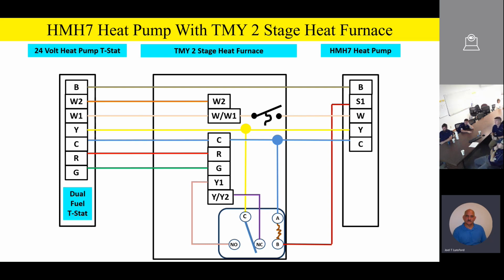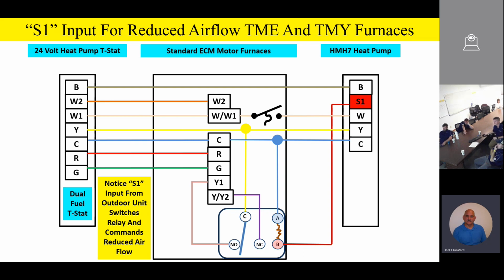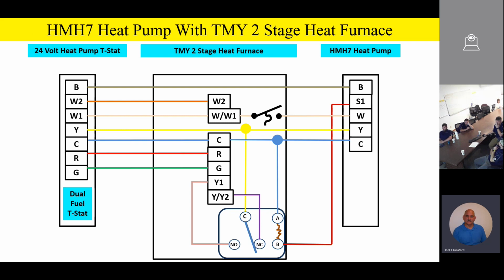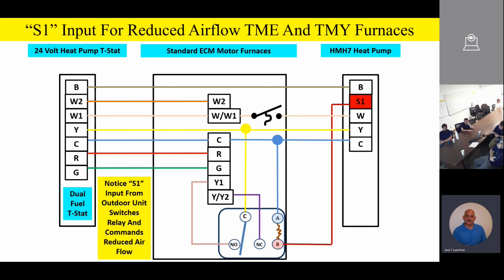Let's go ahead and animate this so you can see how this is going to work. Again, anytime we have an S1 output from the outdoor unit, it's going to energize that relay. Let me animate that one more time for you. Anytime we have an S1 output from the outdoor unit, bang, we're going to switch that relay and command low airflow, or in this case, Y1 airflow. Now, team, please remember when you set up these furnaces, you want to make sure that you set your airflow up for 400 CFM per ton. So if I've got a 2-ton unit sitting outside, I'm going to set it up for 800 CFM. And then your reduced airflow, your Y1 input, needs to be about 60% of your high-speed airflow. So it's pretty straightforward, but the reason we have that relay is to allow the outdoor unit to have reduced airflow on the indoor coil for humidity control and comfort.